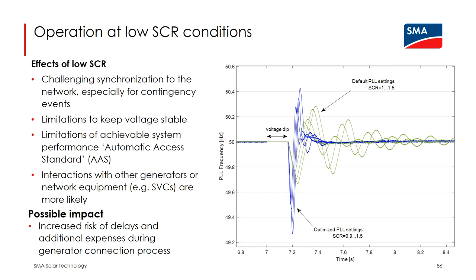As you can see, this always has to be at 50 Hertz, which is the network frequency. Following a contingency event like a voltage dip, which is cleared at roughly 7.2 seconds, you see some kind of resynchronization process, which becomes more challenging under low SCR conditions. This can be tuned to some extent, but when talking about very low SCR, the tuning is more a balancing to whatever gives the best results under very specific conditions.